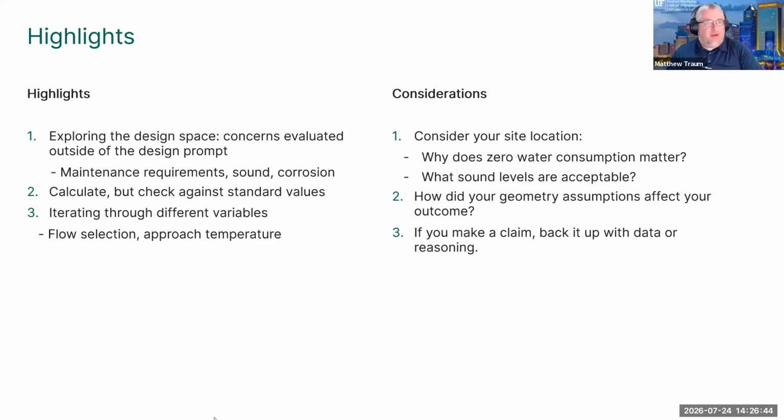Is there some other crazy idea? I kept thinking to myself, maybe you could heat up the air in advance, right? Use the effluent from the turbine to heat up the air and somehow run it through, or use some sort of dehumidification wheel to dehumidify the air before you run it through, just because it's so humid in Florida. Those wet cooling towers are not almost useless. They obviously dissipate megawatts of thermal power, but they're much less effective than they would be in a dry climate.